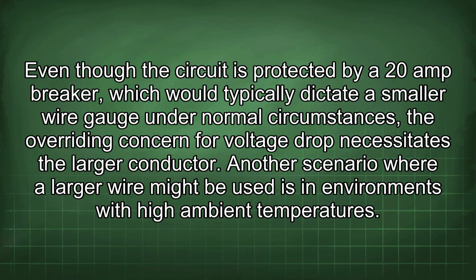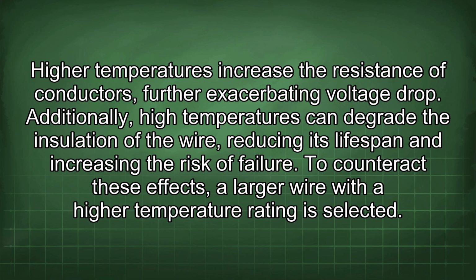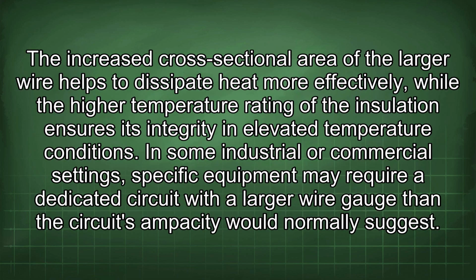Another scenario where a larger wire might be used is in environments with high ambient temperatures. Higher temperatures increase the resistance of conductors, further exacerbating voltage drop. Additionally, high temperatures can degrade the insulation of the wire, reducing its lifespan and increasing the risk of failure. To counteract these effects, a larger wire with a higher temperature rating is selected. The increased cross-sectional area of the larger wire helps to dissipate heat more effectively, while the high temperature rating of the insulation ensures its integrity in elevated temperature conditions.